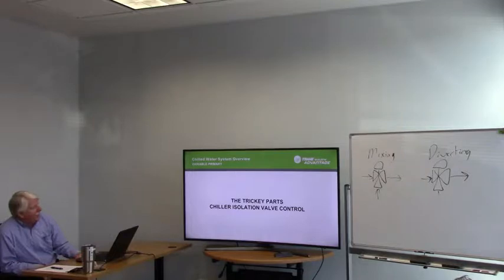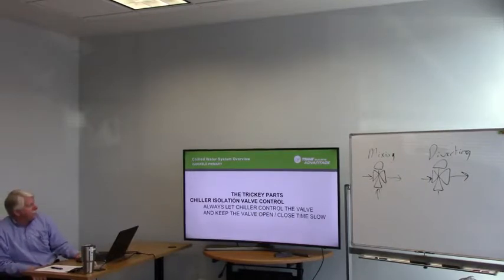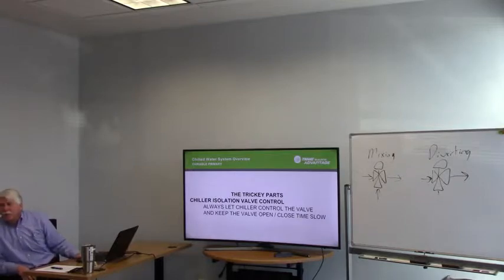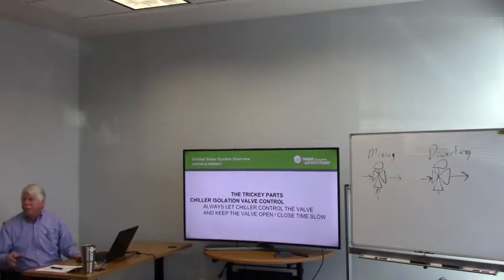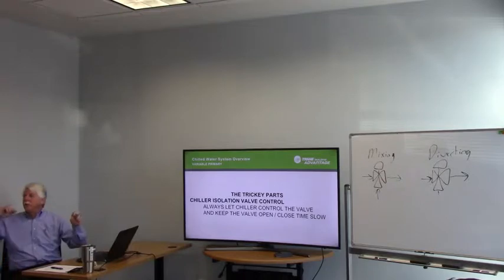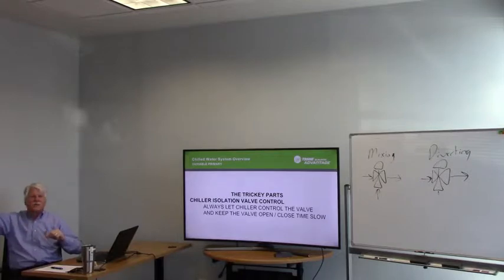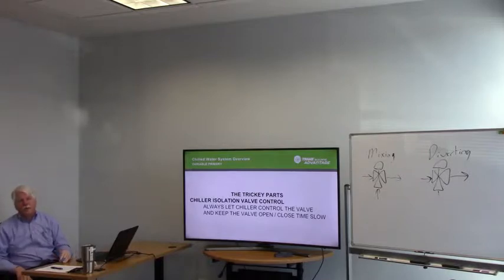Now we're going to talk about the chiller isolation valves. Number one, try to always let the chiller control the valve, because the chiller is going to open and close the valve when it is given a start command and it's ready to start. So you don't have to worry about timing between when you send it a signal. Especially if you've got a UC 600 controlling the valve, and you've got chiller plant control, you've got the timing to get the control out to the 600, you've got the timing of the 600, and then you've got the issue of when the chiller plant is going to do its thing. So it's best if you can try to let the chiller control the valve.